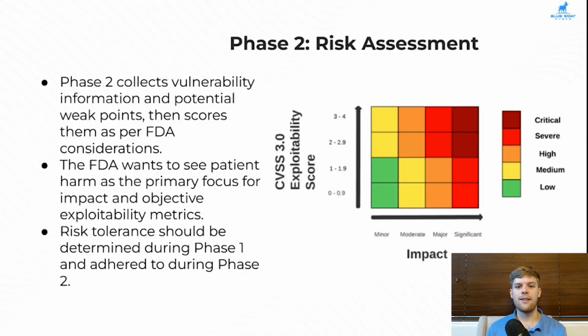The next thing that we're looking at is that risk assessment. So when we're in phase 2, we're collecting vulnerability information and potential weak points, and then we score them as per FDA considerations. So when we're collecting these vulnerabilities, this is through our different types of cybersecurity testing. How are we finding the weak points in a system? And then how are we looking at what is really the impact? What can go wrong? How bad of an issue is this? Now, the FDA wants to see patient harm as our primary focus. And so that's essentially saying, if this cybersecurity vulnerability is realized, if an attacker can pull off this attack, what's going to happen to a patient?